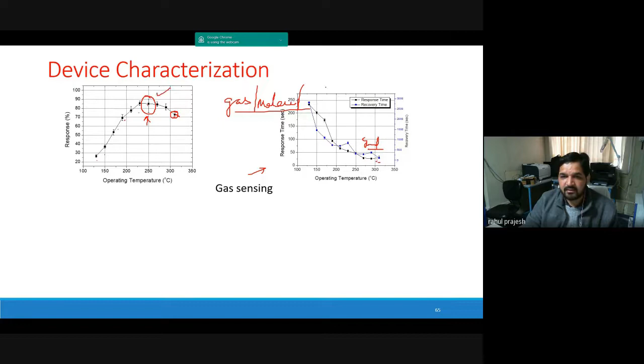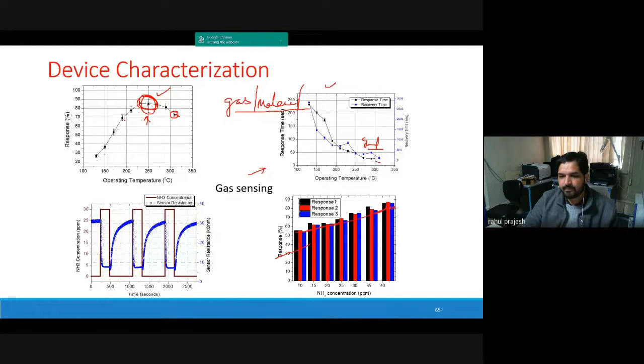Then you can check the repeatability of the sensor by giving multiple pulses of the gas, and then finally you calculate the input concentration and the response you are getting, and it should be linear.